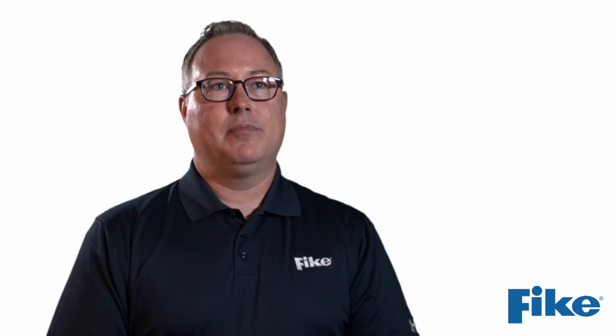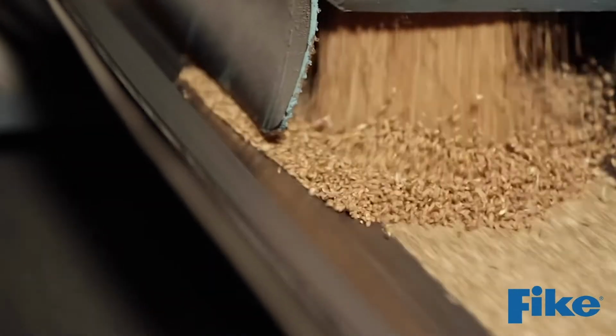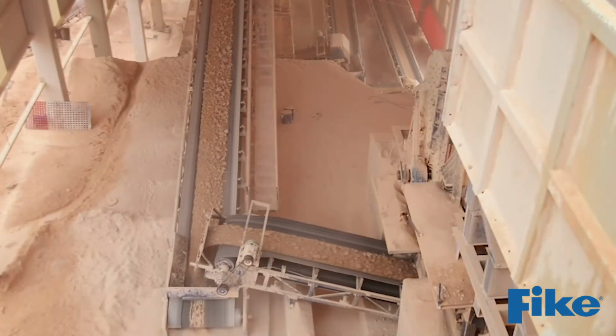The next step is to identify and evaluate the various types of dust you have on site. So this starts by looking at all the solid particulate materials handled on site. You come up with a list of the dust, and then you see what data you have on that dust. So you can look at safety data sheets, you can look at prior testing, you can look at online databases, or NFPA standards might have data on specific dust. And oftentimes you might need to conduct additional testing to get the data that you need.